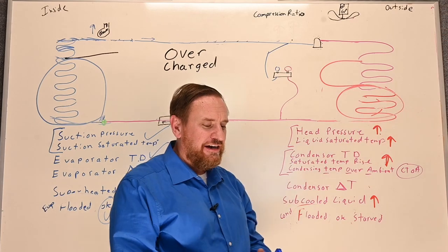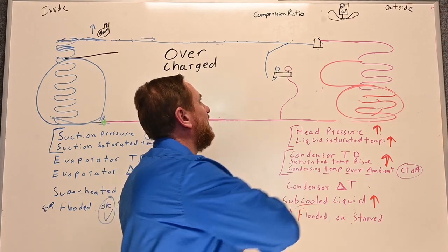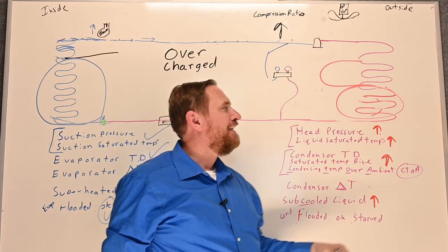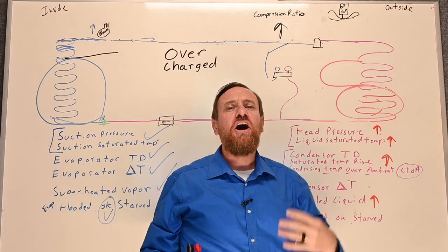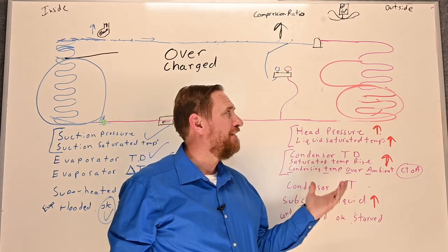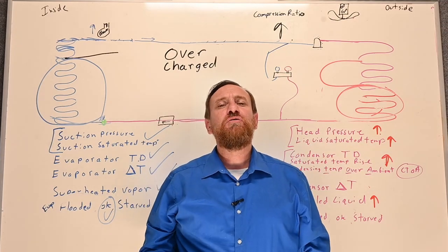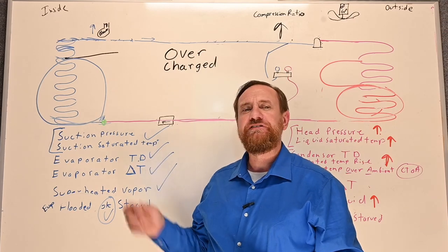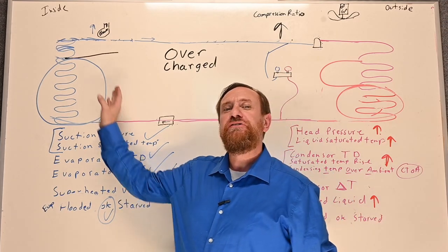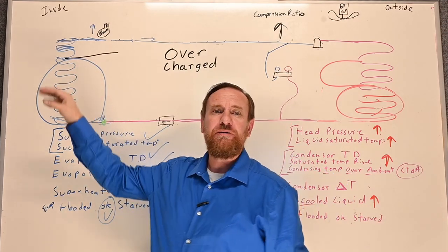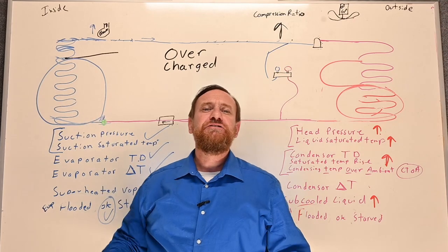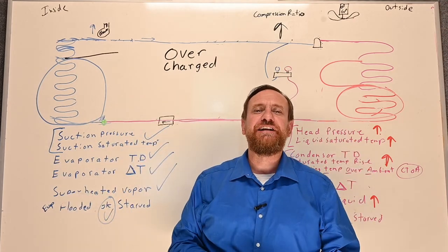Even if you overcharge a TXV system — which is still bad — the TXV or EXV will try to maintain that evaporator coil, which is fantastic. But all the problems are still happening out here on the condenser side. More pressure causes a higher compression ratio — we're stacking refrigerant to a higher temperature outside, more vibrations, more work for the compressor. That's why with TXVs, we look at sub-cooling first. If we see too much sub-cooled liquid, there's going to be an issue. But we also still want to check superheat to confirm it's doing its job. That's how an overcharged system affects a thermostatic expansion valve.